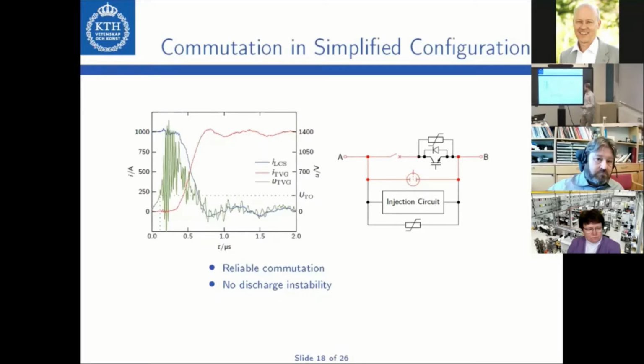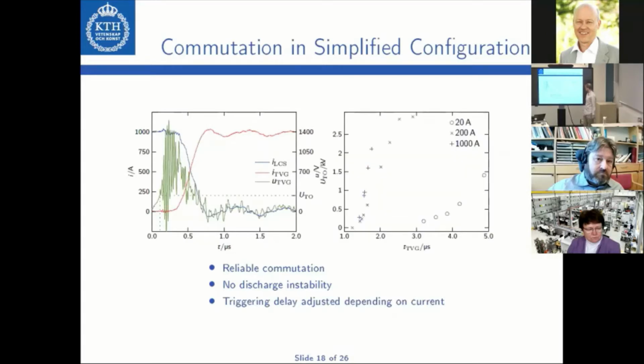The thing is, though, that the turn-off voltage of the snubber depends on the current level. This means at a lower current level, the turn-off voltage of the snubber increases more slowly. Therefore, the delay between turning off the LCS and triggering the triggered vacuum gap has to be adjusted. Here you can see this for various current levels. For instance, for this 20 amp level, the triggering delay is approximately 2 microseconds more than for the higher current levels. In a practical DCCB application, it would be required to have some kind of monitoring system that adjusts the triggering online.